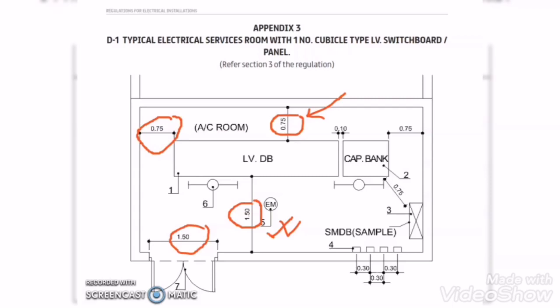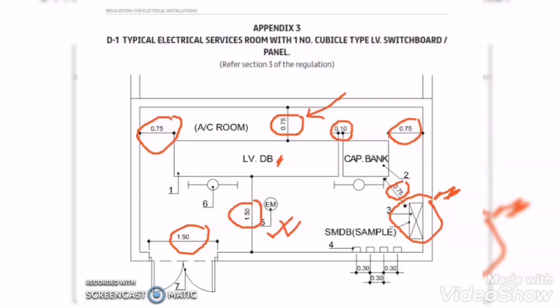If we are placing any panel adjacent to the LV panel — it can be another LV panel or a capacitor bank for the same LV panel — then the minimum distance between the two panels must be maintained at 0.10 meter, that is 10 cm. Similarly, the distance between the side wall of the electrical room and the panel must be maintained at 0.75 meter. If we are placing any other panel like an SMDB or ATS panel, we have to make sure that the panel door does not clash with the other panel during opening and closing.